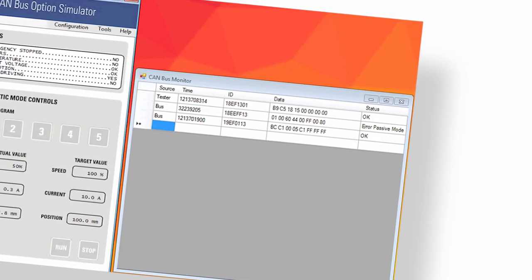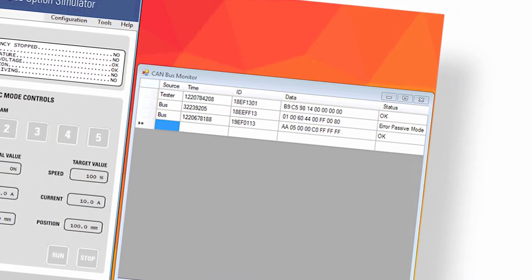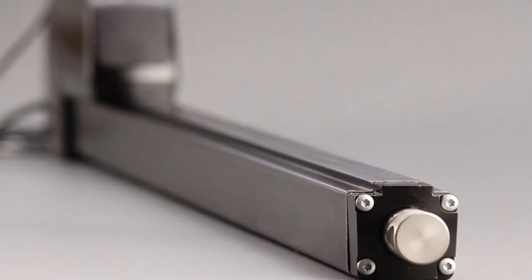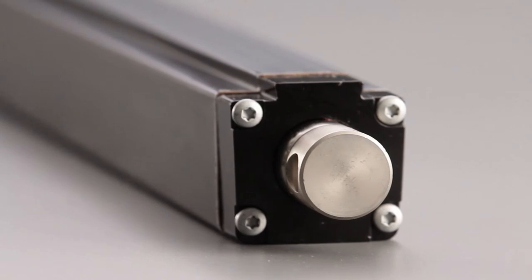The Electrak HD gives you better design flexibility, enhanced controllability, and it's less complicated to install and maintain. With the Electrak HD, we've also introduced our new electronic monitoring package. This monitors current, voltage, and temperature simultaneously to make sure the Electrak HD is running at its optimal performance in any condition. If running outside of its desired specs, the actuator will shut down to ensure its safety and your application's safety.